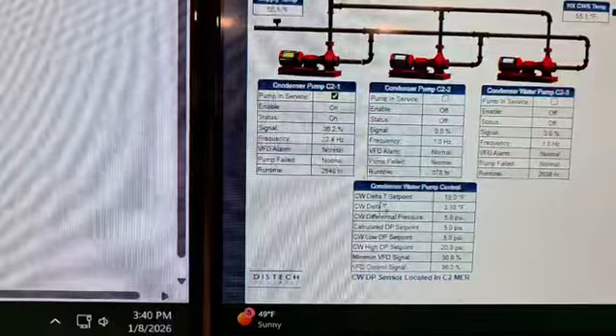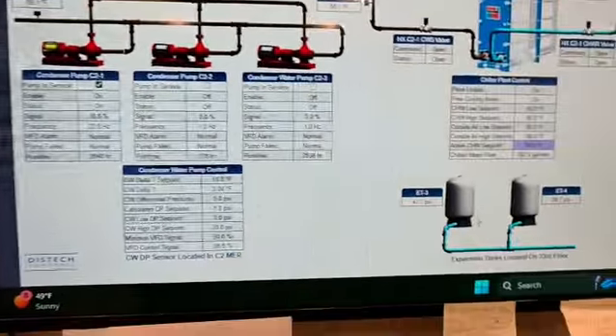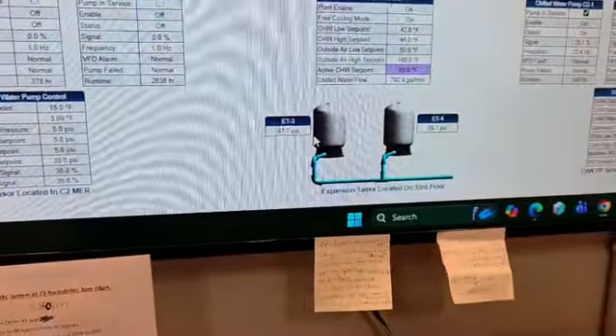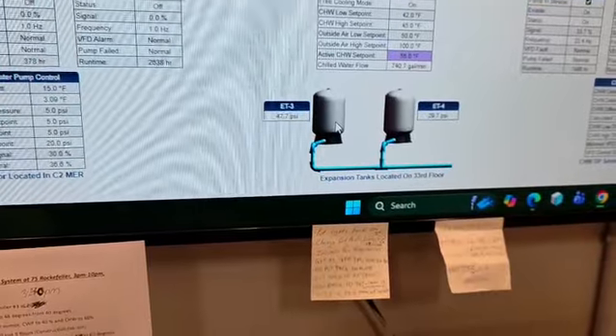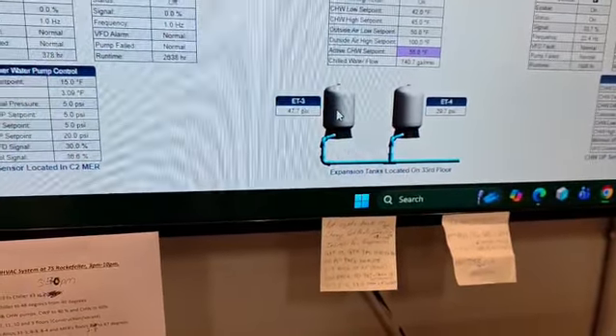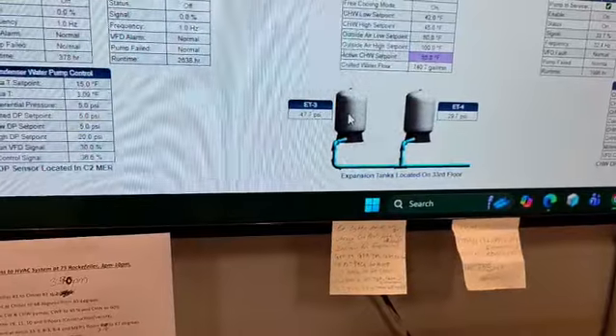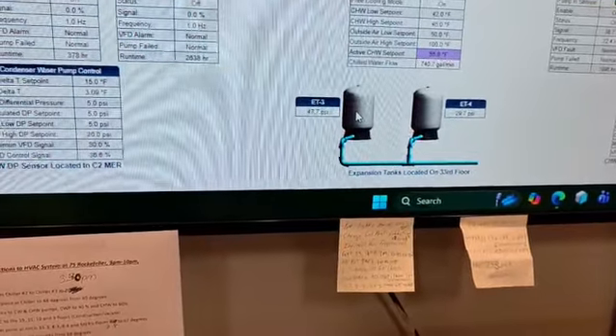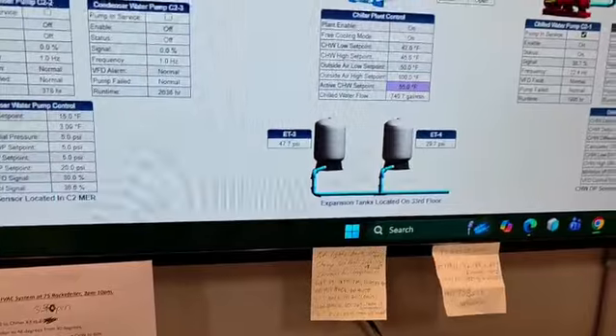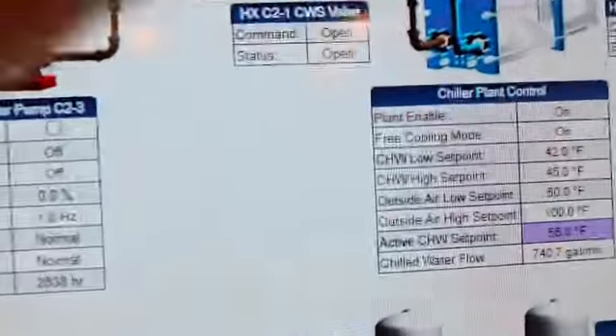Cool. And then you have your expansion tanks. If the water gets too hot, it needs to go somewhere. You don't want to lose the water, so you send it to an expansion tank. Then when the pressure lowers, the tank releases the water and it comes back into the system. No biggie. What about these set points here?